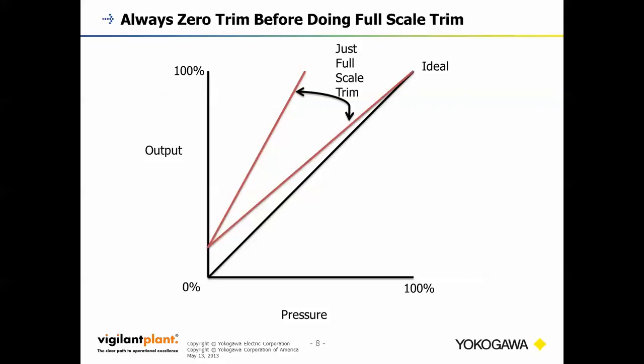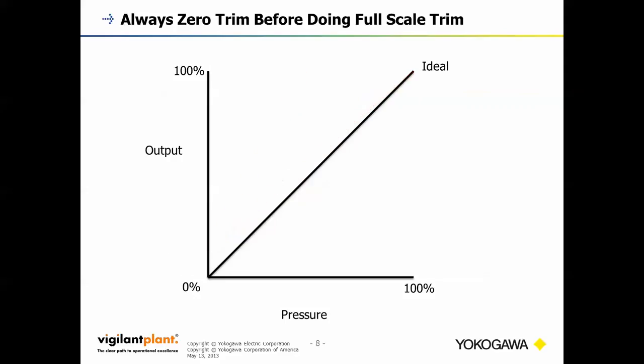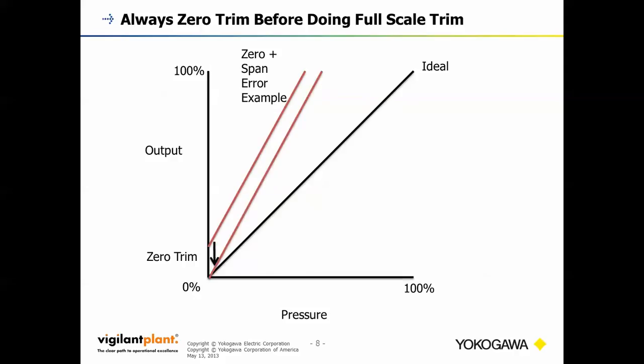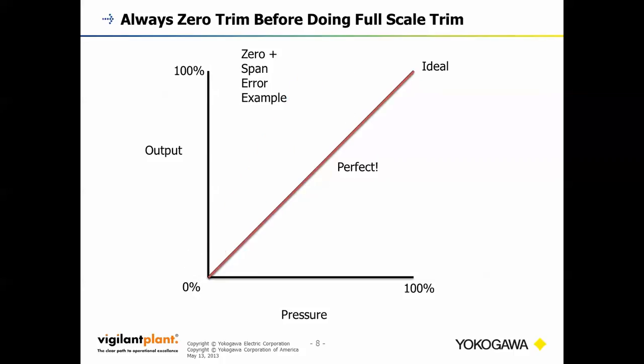If I just do a full scale trim, I'll adjust my slope to match the ideal at 100%, but I still have that 0 error. So that 0 offset hasn't been corrected. So ideally, with a 0 plus span error example, or any time, you do a 0 trim to get your 0 offset back online, and then you do a full scale trim to get the slope perfect with the ideal line. Again, that's a good graphical representation of why you always do a 0 trim before doing a full scale trim.